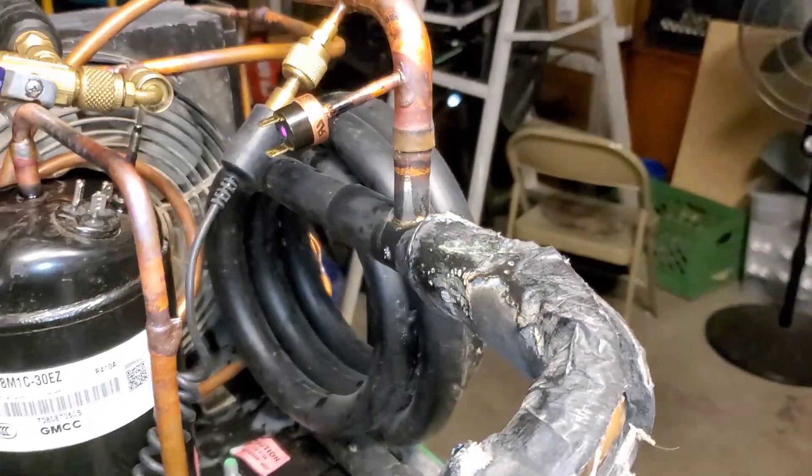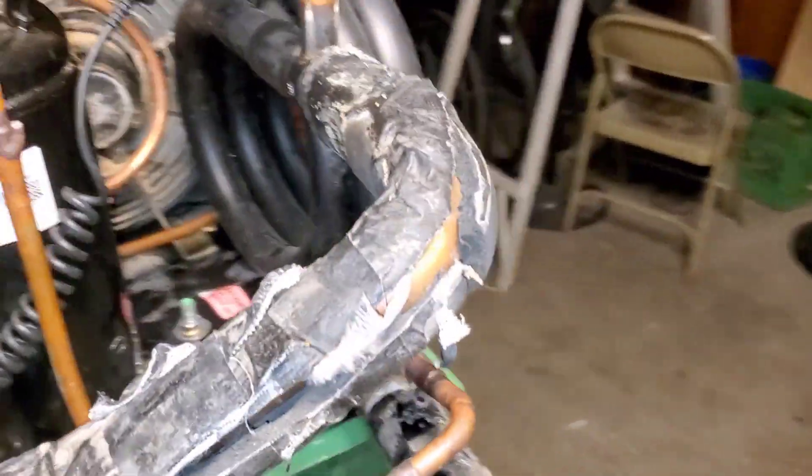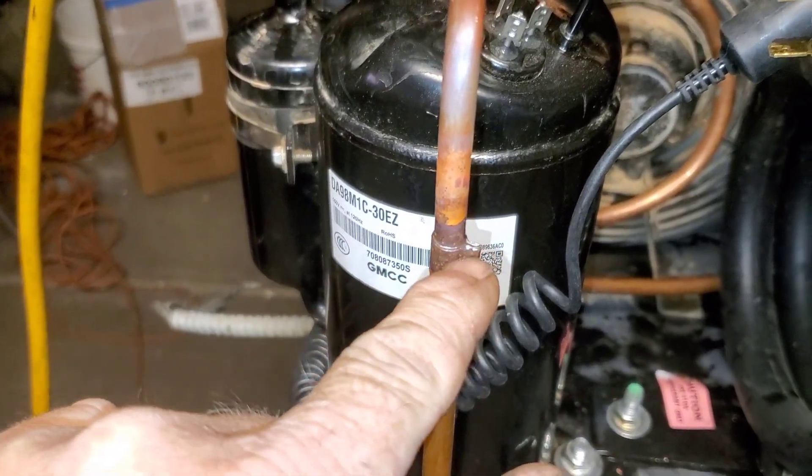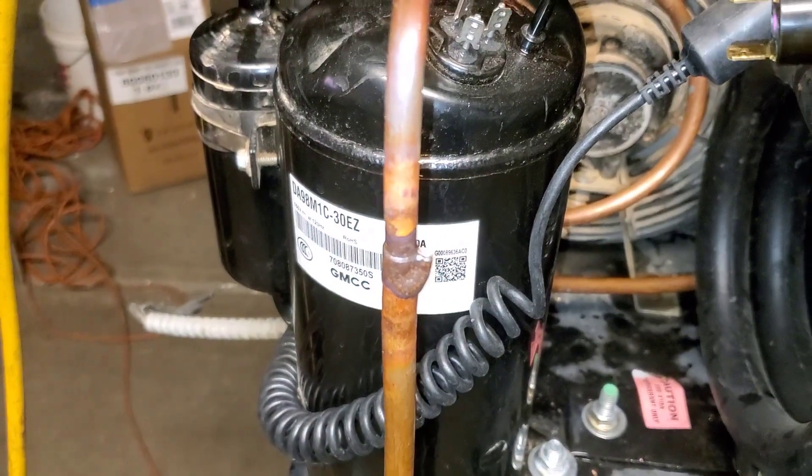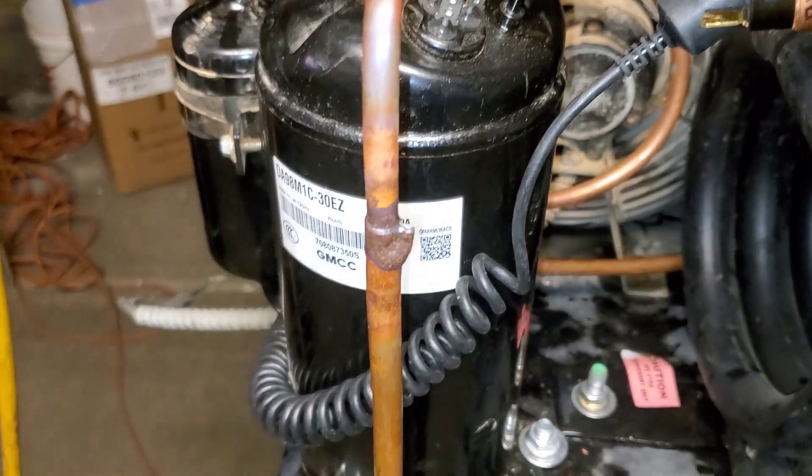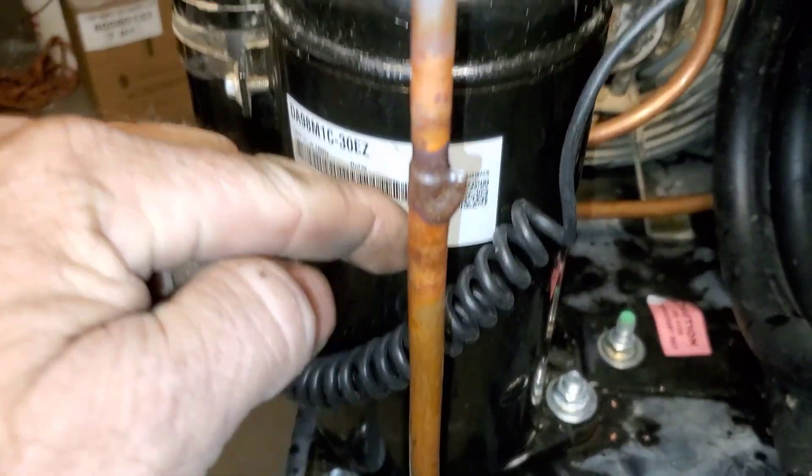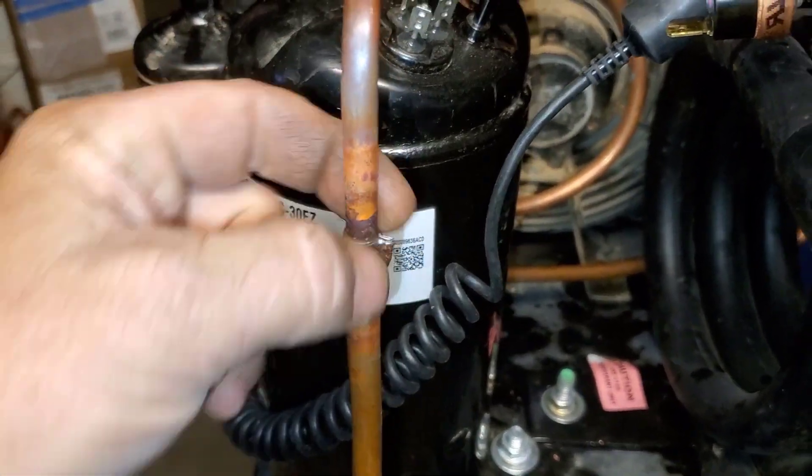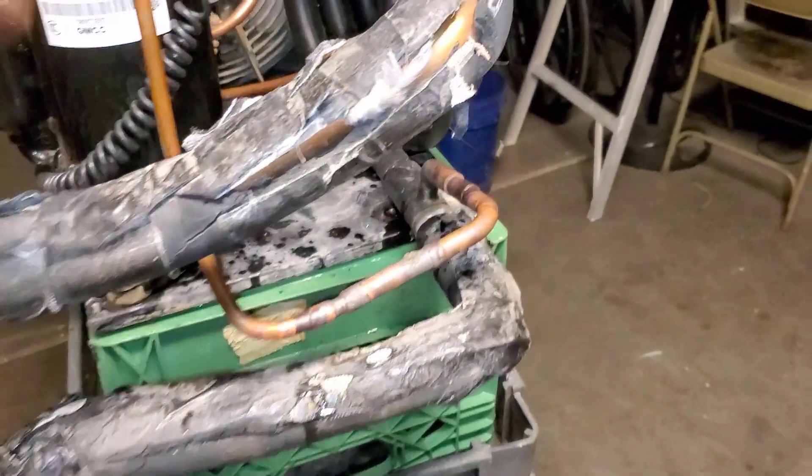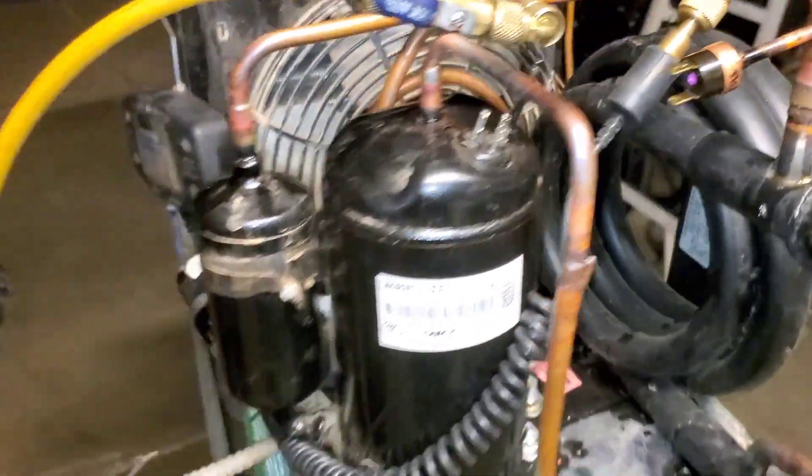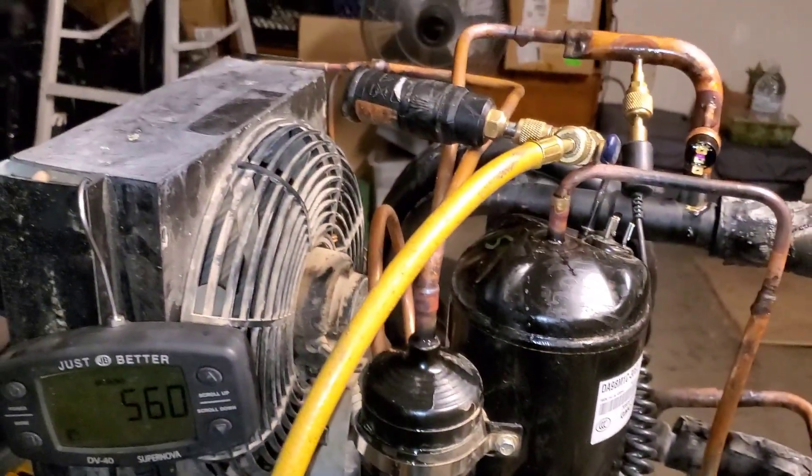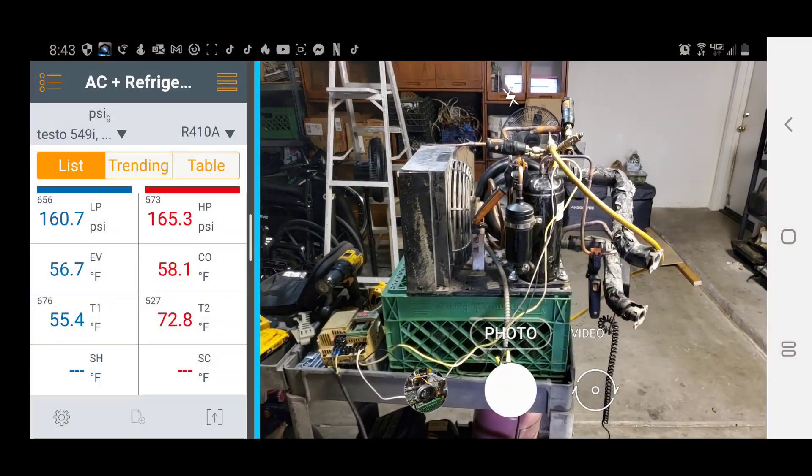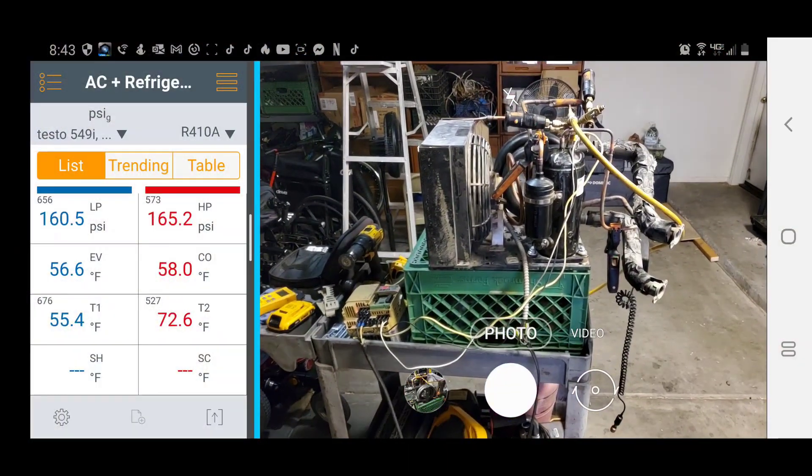Only thing is, I didn't have—this is five-sixteenths—I tried to kind of pinch this. It works. Some people probably talk shit, but I didn't have any five-sixteenths pipe and that goes into the three-eighths. So I swaged the three-eighths and then had to bend it. I put a little bit of refrigerant in it so I should be able to start the compressor.